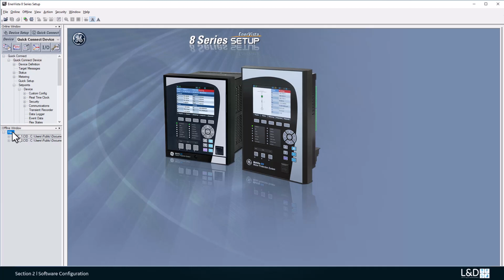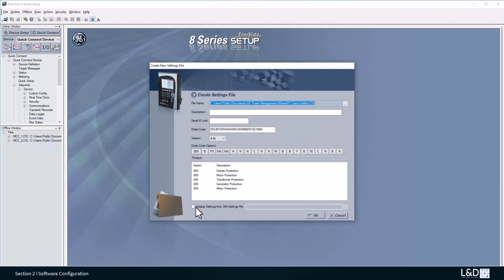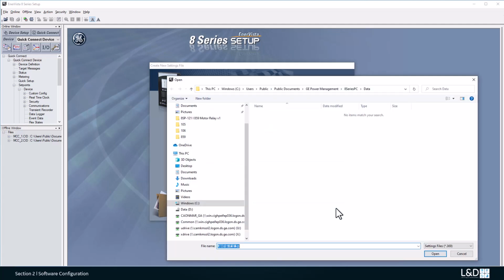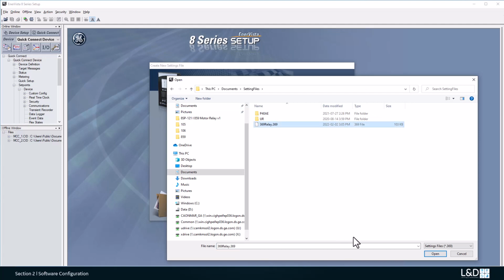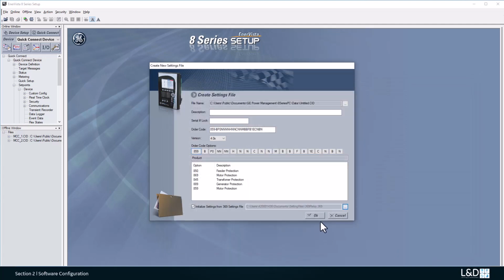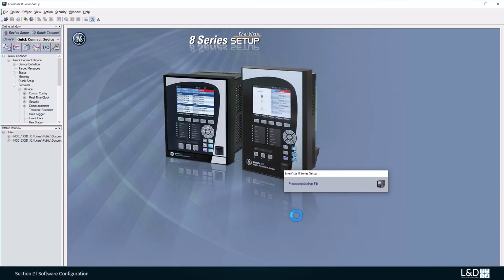import a 369 setting file. To import the 369 setting file, we can right-click the mouse and choose new setting file. At the bottom, there's one checkbox: initiate setting file from 369 setting file. Check this box, click the three dots, and go to find the setting file folder. We got the 369 relay.369 setting file, then click open, and then just click OK. It will do an automatic conversion of the 369 into an 859 setting file.